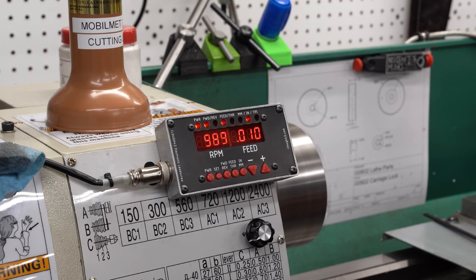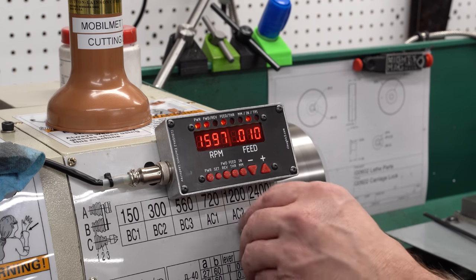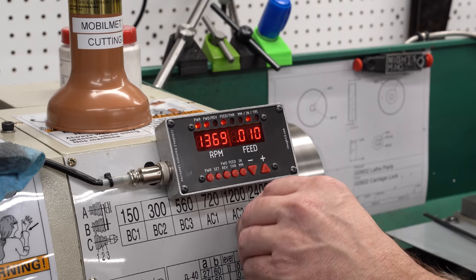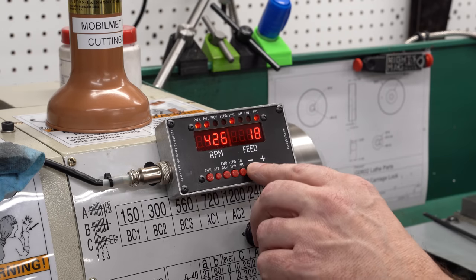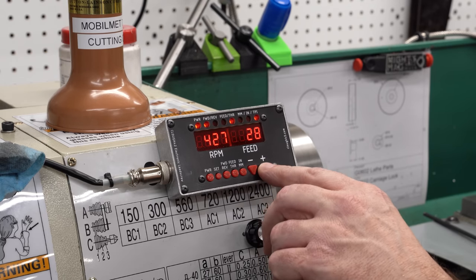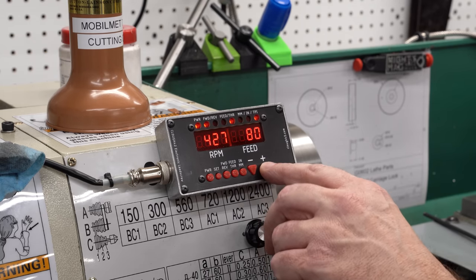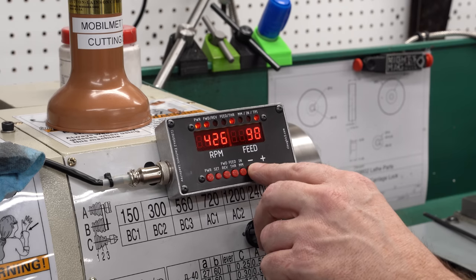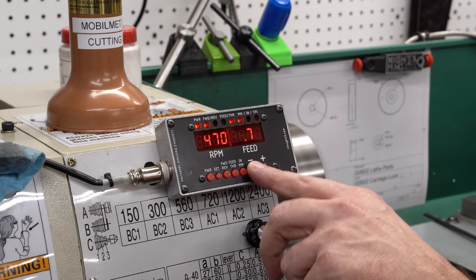Now, no matter how much noise filtering I try to put on the board itself, it is always going to be possible with a high power, high frequency system like a VFD on a three-phase motor to generate enough noise to overwhelm the electronics. There's really no way to prevent against that entirely. So this filtering is not a substitute for good wiring practices.